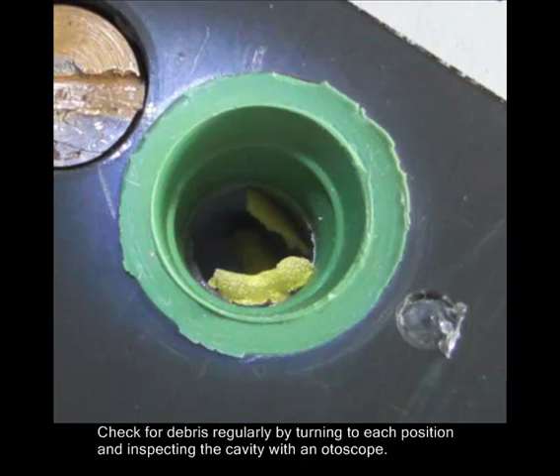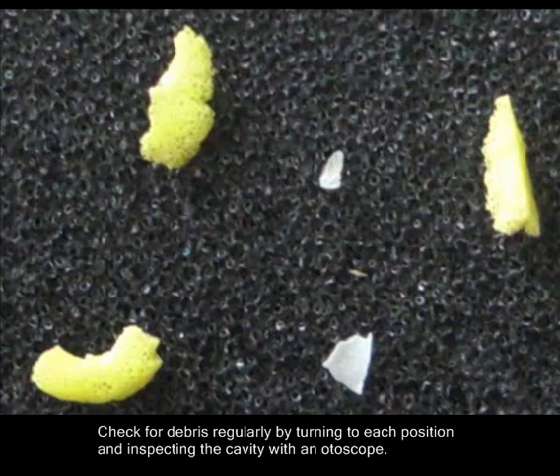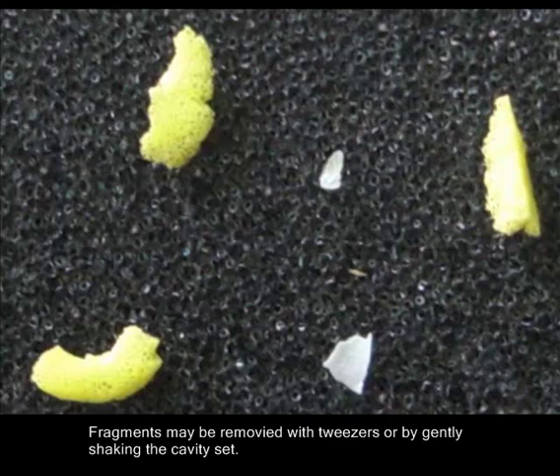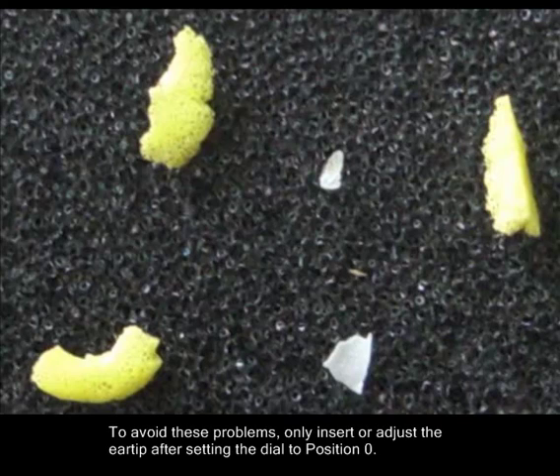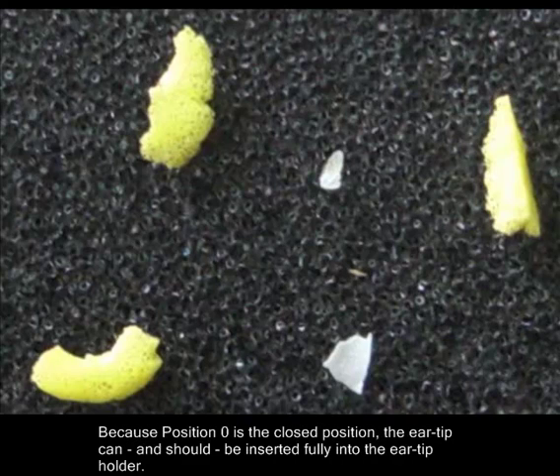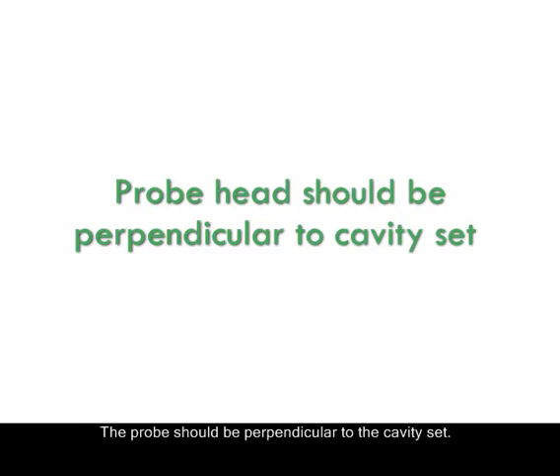Check for debris regularly by turning to each position and inspecting the cavity with an otoscope. Fragments may be removed with tweezers or by gently shaking the cavity set. To avoid these problems, only insert or adjust the ear tip after setting the dial to position 0. Because position 0 is the closed position, the ear tip can and should be fully inserted into the ear tip holder. The probe head should be perpendicular to the cavity set.